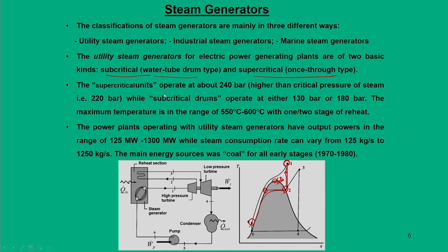Supercritical unit boilers operate at about 240 bar, just higher than the critical pressure, while subcritical units operate in the range of 130 to 180 bar, with maximum temperatures in the range of 550 to 600 degrees centigrade. These units produce power in the range of 125 to 1300 megawatts, for which the steam consumption is about 125 to 1250 kg per second. The energy from coal is used to produce this power.